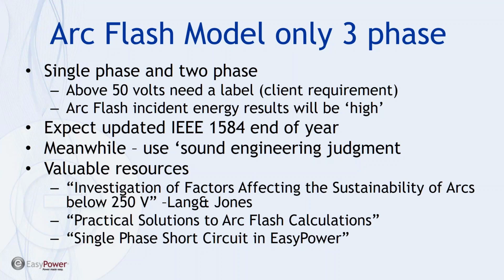single-phase calculations. Meanwhile, in addition, we have it on good authority that there will be an updated 1584 by the end of the year that is a little bit more specific than the vague reference we currently have for low voltage arc flash. So even in the current standard, there is wording that says use sound engineering judgment as you're dealing with any of these adjustments or tweaks to the IEEE model. And so that's why I am offering these handouts.